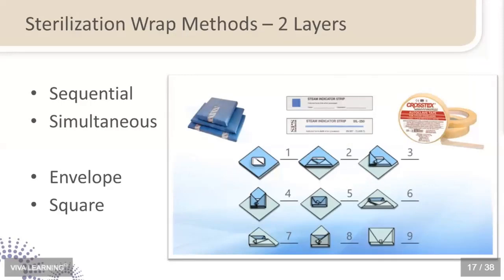That has to do with your positioning the cassette at the center of almost the diamond shape, and then you're going to first of all bring down that top fold of the diamond across the top of the cassette, and then you would bring up the 2 sides, and then finally the bottom gets folded in and tucked with a tab. This envelope method is the recommended method for small to medium-sized cassettes. If you are working with a large cassette, a surgical cassette, some restorative cassettes, an implant cassette, a periosurgery cassette, a square wrap method, sometimes people call it a parcel method, is recommended with larger cassettes.